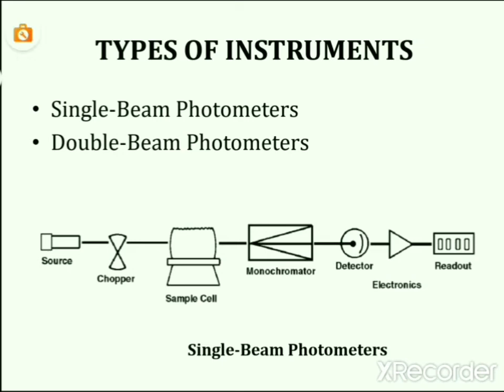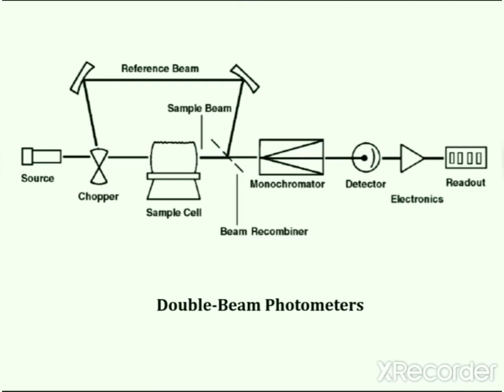In the double beam system, the reference beam serves as a monitor of lamp intensity and the response characteristics of common electronic circuit. Therefore, the observed absorbance determined from a ratio of sample beam and reference beam readings is more free of effects due to drifting lamp intensities and other electronic anomalies which similarly affect both sample and reference beams.